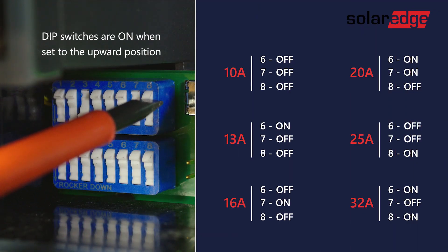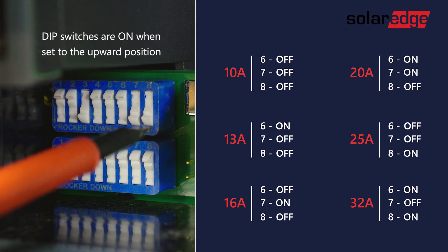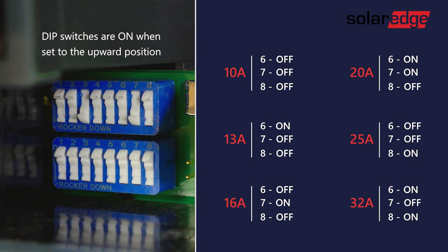In order to adapt the maximum current to the installed line circuit breaker, a configuration via the dip switches is necessary. To move the switches you should use a flat screwdriver, and for alternative setups of current use the quick installation guide. Alright, we have our dip switch set.